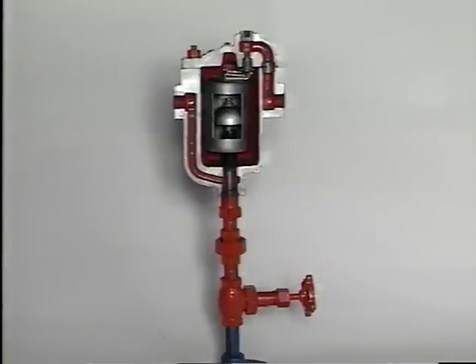Prevent the thermal shock that is generated by such a design by substituting a constant purge device, such as a differential condensate controller, for the steam trap.